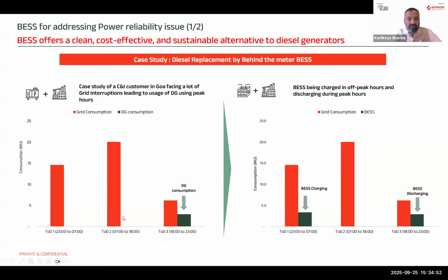Instead of diesel generators, which cost them about 30 rupees per unit, if we simply install a battery that can charge during the night from 11 to 7 a.m. when power is cheaper, and discharge during the day—even for a single cycle—they end up saving more than 50% on the price of the expense they make on diesel generators, and this can also be availed for other uses. In fact, power quality also improves, which goes on to improve the quality of production.